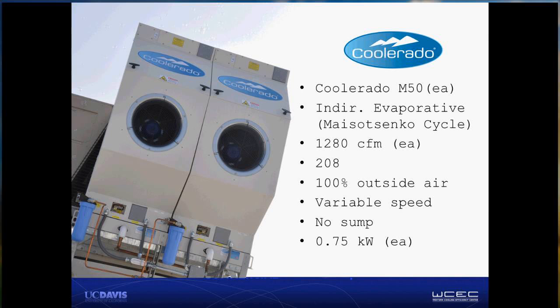Remember that these systems operate as 100% outside air. They're variable speed, so they can adjust to different ventilation airflow needs, and at the same time they can allow for a very efficient part load operation by running the fan at part speed. Coolerado, you should note, doesn't use a sump. It's a sort of once-through system. They measure outside air conditions and make a sophisticated prediction about how much water will evaporate and how much water is needed to wash away a high concentration of minerals so that they don't end up with solid deposition inside the heat exchanger. And then that water drains out of the heat exchanger and down the drain.